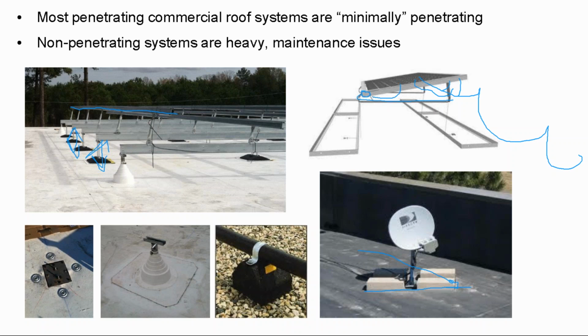But the end result is you get standoffs coming out of the rooftop, and then conduit pipe blocks, although these are very robust pipe blocks, lifting the sub rack up off the rooftop before putting the broader rack on top. The end result being the module is a good 1.5 to 2 feet up off of that roof deck.